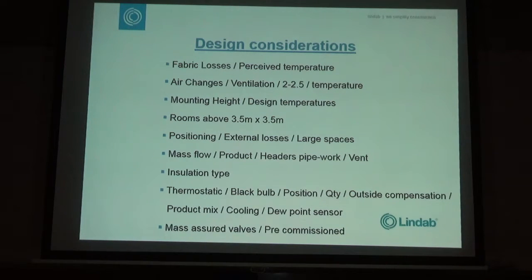So if you bring your air changes in, you have to temper it with some sort of heat because your radiant panels aren't going to heat it. Unless, I have done a job where the fresh air has come into the ceiling void, we take the insulation off the radiant panel, and that convective heat of the radiant panel has warmed up the air that's in the void, and then it's been pressurised. So you have to take precautions to provide some sort of tempering to your fresh air if you've got high air changes. Rooms above 3.5.